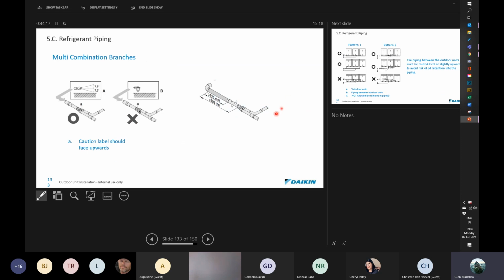Right, so we have a look at those over there, just to go over that one more time. The ref nets at the condenser must be horizontal. You do need to have a minimum of 500 millimeters of straight piping entering into the ref net, but coming off of the ref net, you do not need 500. You can bend straight away and go in. So effectively, this bend must be in line with the service valve that it's going to connect onto. All right, so just keep that in mind. You may not install them vertically like that. Okay. If we come to site like that, we are going to make you change them.